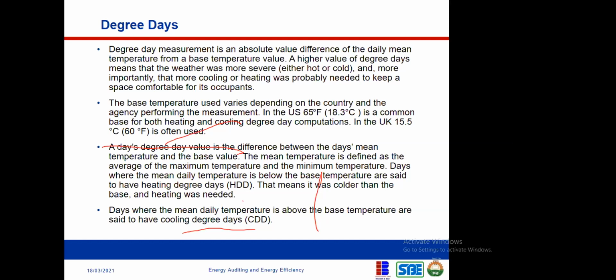Then if you're in a cold weather, maybe in Europe or America and the weather is very cold, the reverse is the case. It becomes heating degree days. Normally they will use something like 18, but let me use 24 for simplicity. If you have 24 as your base temperature and the weather is 18, you're going to heat up the environment to come up to 24 degrees. So the heating degree day will become 24 minus 18, which will give you 6 as well. That's what heating degree days and cooling degree days are. You can compute this over one month, one day, or one year, so it doesn't matter; the time period varies. Let's go to the next slide where we'll show you an illustration of how this is done.